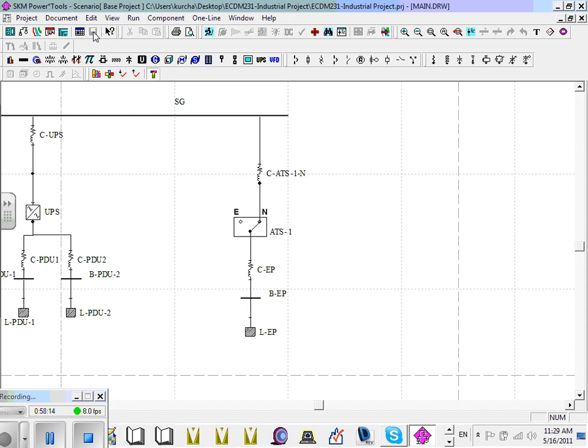Make sure you save. My goal, guys, before you go today is I'm going to run a short circuit analysis on it. That's why I want to build it. And then tomorrow, Mashad will build on what I did, and then Wednesday, I will do the coordination. It's very easy to do the short circuit analysis. I'm going to put data just to fill it right now, and then you guys update it to the best of your ability. I'll show you a very easy way of putting data.